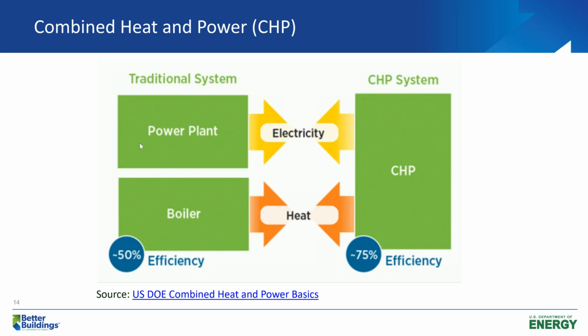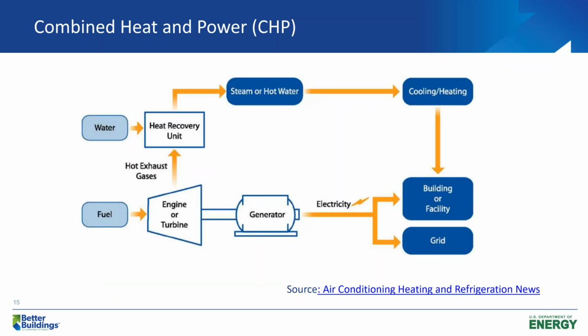Here's an example of a common system configuration in CHP, with a gas turbine heat recovery unit to capture heat from the turbine's exhaust stream. You have this output of electricity to use in the building, but also the output of exhaust gas with heat recovery to serve your heating and hot water loads in the building. This is where that efficiency comes into play.